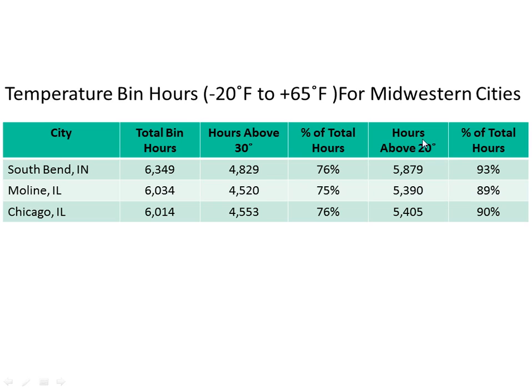If I take it one step further and look above 20 degrees, 5,400 of my hours are above 20 degrees. That's 90% of my heating hours. So when you normally size a furnace, obviously you're not sizing it for 20 or 30 degrees outside. You're sizing it for 0 or -5 or -10, or whatever your normal standards are at your company. But if you're sizing for a -10 degree day, and it's really only a -10 degree day for a couple hours out of the year, in this example I only have 600 total hours below 20 degrees. For the whole year, 600 hours are below 20 degrees, 10% of my heating time. And I'm sizing a furnace for -10 or 0.